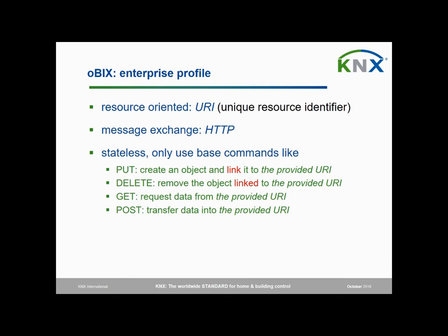Okay, let's have a look at some further details for the OBIX enterprise profile. It is resource oriented. That means we will use the so-called URIs, which stands for Unique Resource Identifier. The messages will be exchanged using HTTP, as said before. This profile is also stateless, which means we will only use some base commands, like the few examples here on the slides. So the put command, delete, get, post.